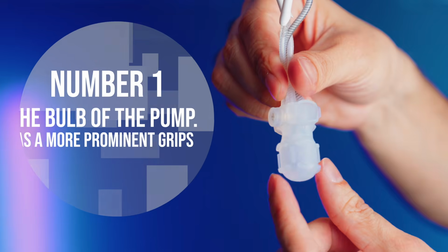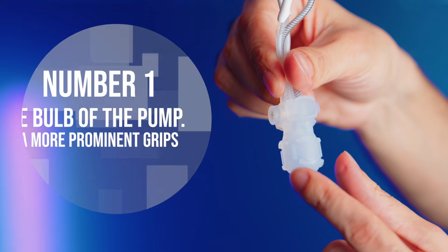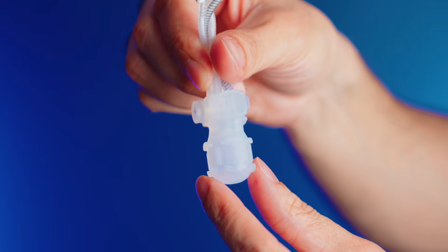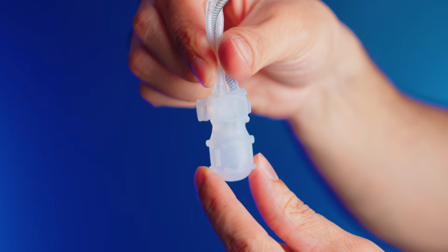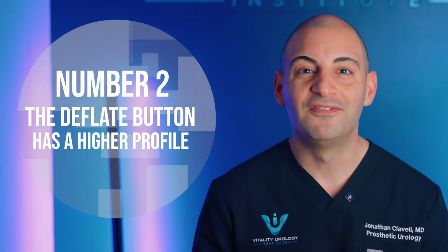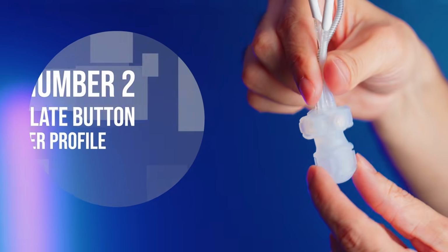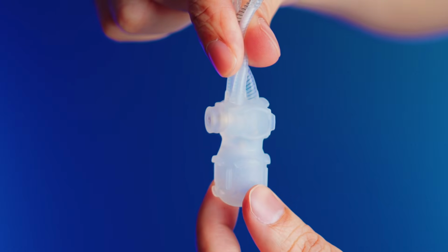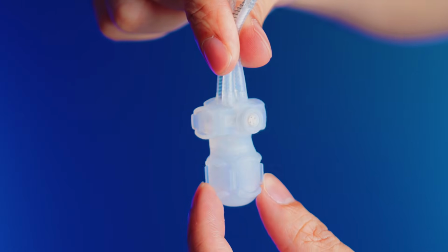Number one, the bulb of the pump has a more prominent grip, which is intended to make it easier to locate the bulb and squeeze, especially for men with dexterity issues. And number two, the deflate button has a higher profile. It is slightly bigger, which is intended to provide tactile feedback, which should allow men to know when you have activated that deflate button. The feedback that it provides is a subtle click that you may feel when you press the deflate button. Even though I have personally found that click to be extremely subtle and difficult to truly feel, it is fairly obvious when you hit the deflate valve because you will feel the cylinders deflating and getting softer.